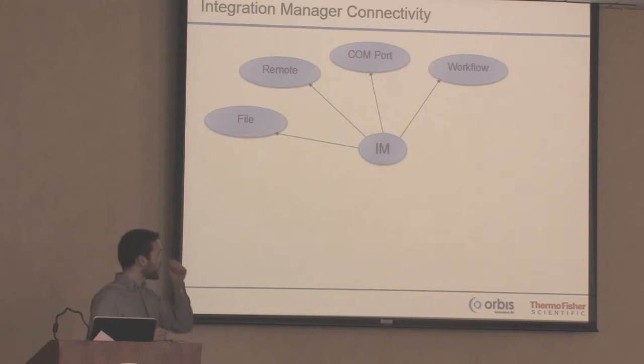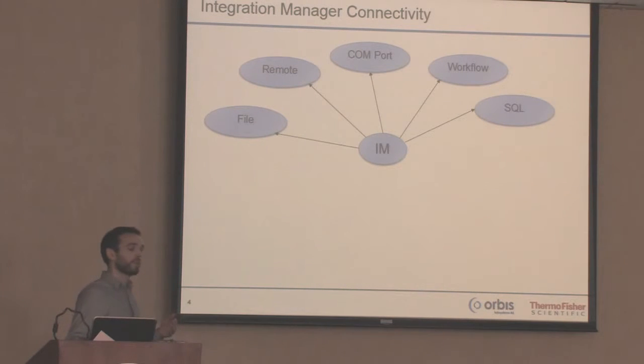We then have a workflow agent, which is new to Integration Manager 3.1. This utilizes Microsoft Windows Workflow Foundation, which allows you to build a process. Rather than with the COM port integration, where you have a single result being passed, with the workflow you can build a conversation between your instrument and Integration Manager, and it will trigger certain reactions, certain activities. We have the SQL agent, which enables connection to databases. You can connect to Oracle, SQL Server, or Console EDC.